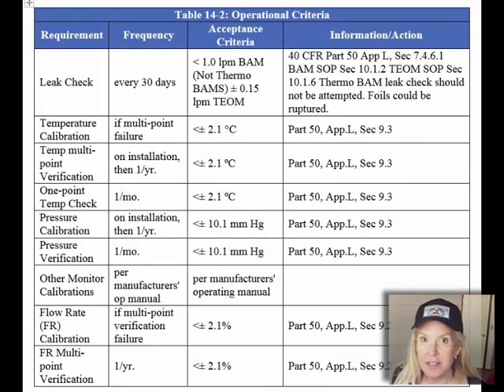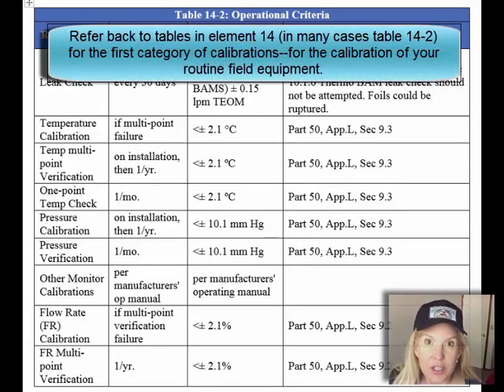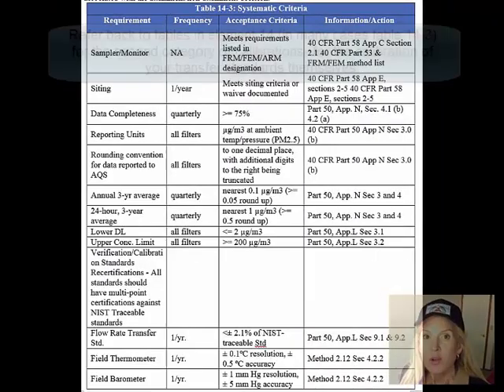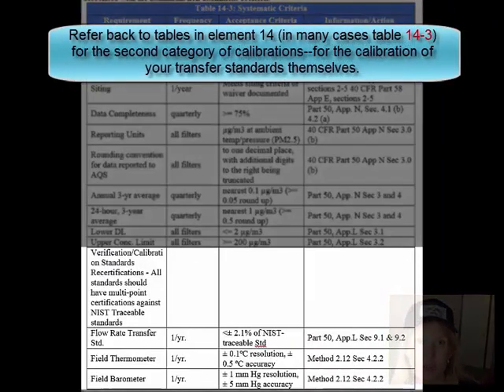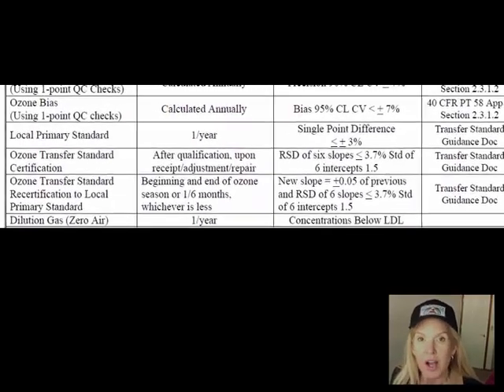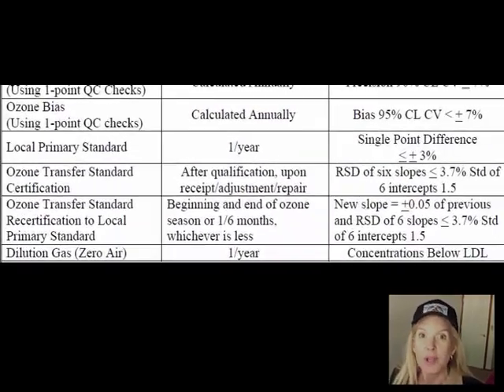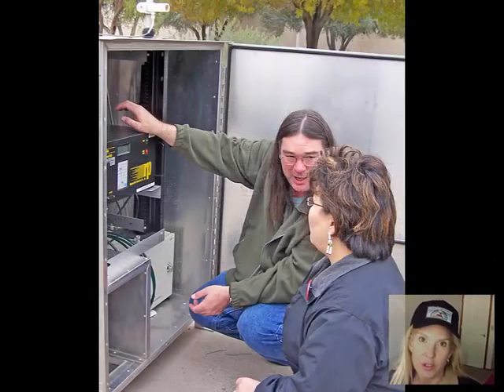So this section has to discuss 2 kinds of calibrations. One are the calibrations that your field instruments undergo and whatever the requirements are for those. Then you also have to consider your flow rate transfer standards, your temperature transfer standards, those sometimes handheld standards that you compare against your field instrument. Those also have to be verified and calibrated, a lot of times annually. In most cases, the manufacturer will do that for you. A lot of programs have 2, or maybe you can borrow a standard if you don't get yours back from getting calibrated before you have to use it again.